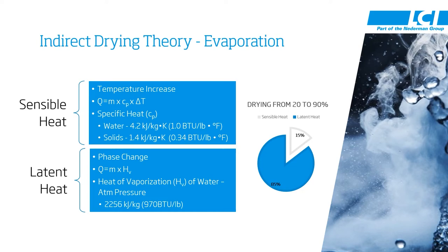In order to calculate the sensible heat, we use the equation Q — heat — equals mass, in this case the mass of sludge coming into the dryer, times Cp, the specific heat. We have to use the mass fraction of the water and the solids inside that sludge, times delta T. This delta T is the temperature from the incoming sludge to get the sludge up to boiling.